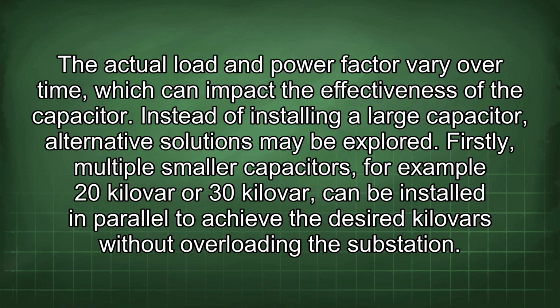Instead of installing a large capacitor, alternative solutions may be explored. Firstly, multiple smaller capacitors, for example 20 kVAr or 30 kVAr, can be installed in parallel to achieve the desired kilovars without overloading the substation.